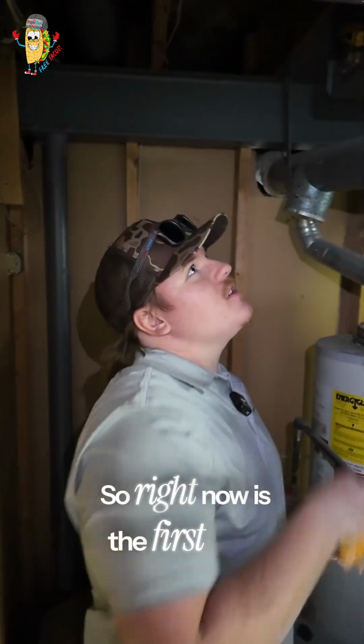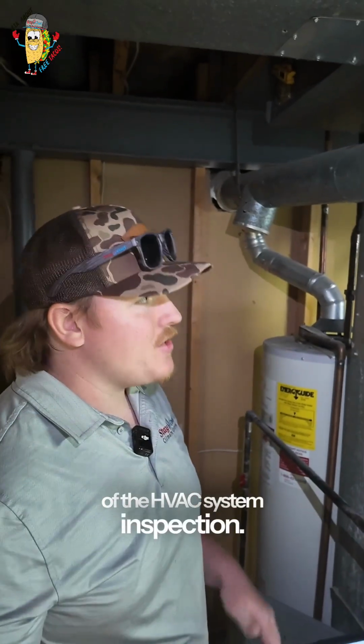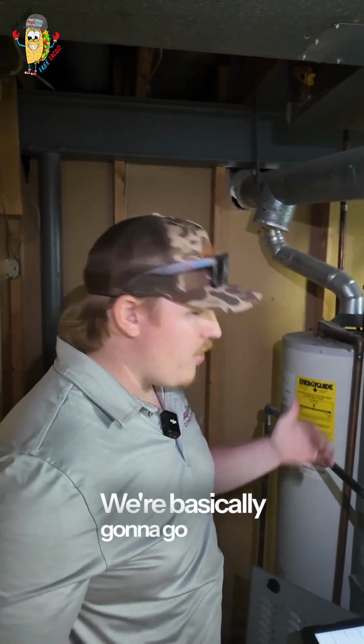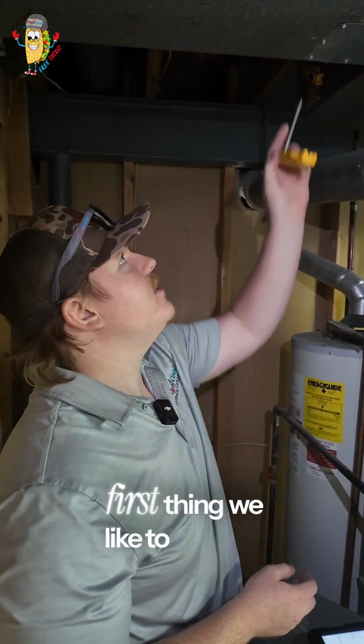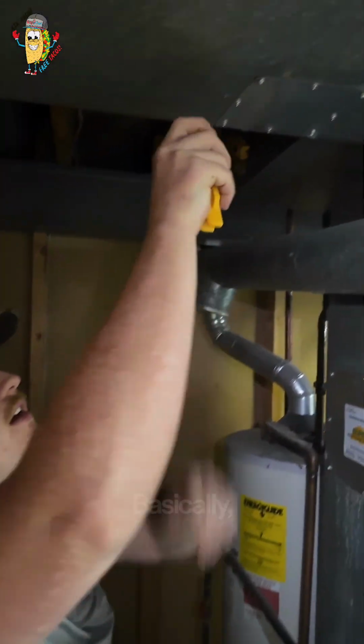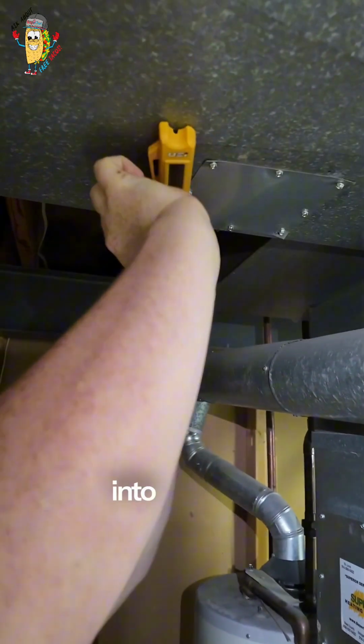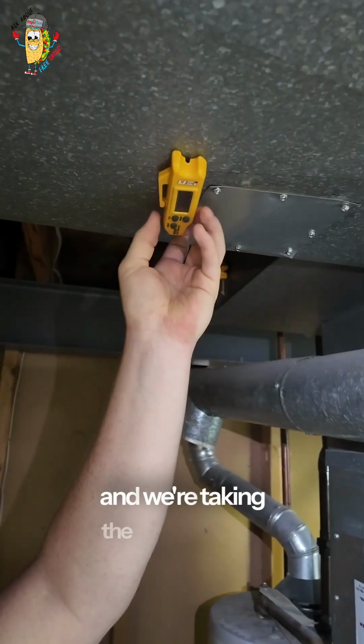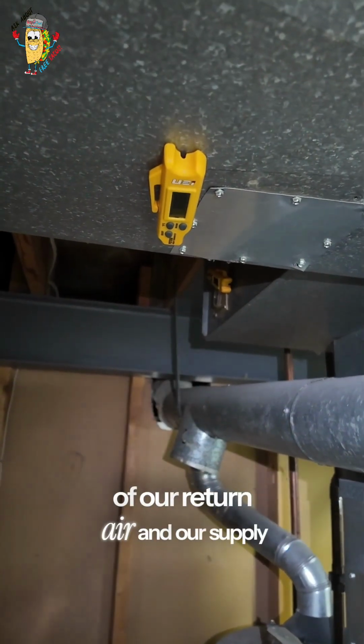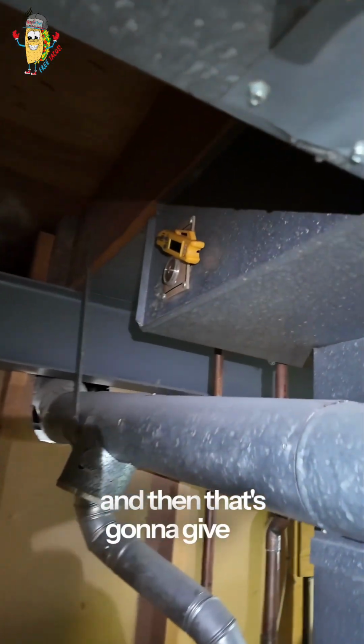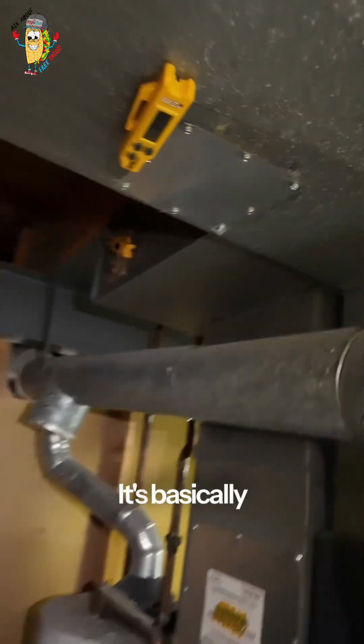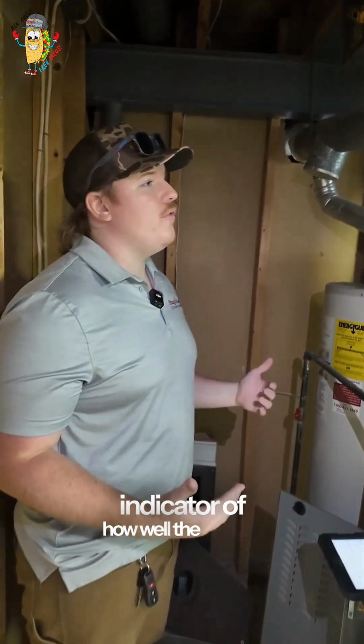So right now is the first step of the HVAC system inspection. We're starting with the heat. We're basically going to go through our full checklist. First thing we like to do is we always like to get a temperature rise. Basically, we slide our thermometers into the ductwork like this, and we're taking the temperature of our return air and our supply air. We're going to subtract the difference, and then that's going to give us our temperature rise. It's basically a good standard indicator of how well the furnace is operating.